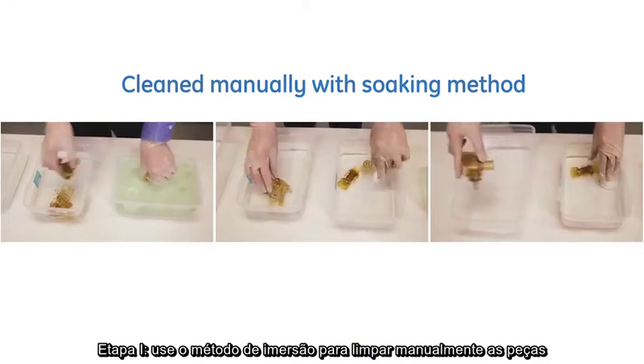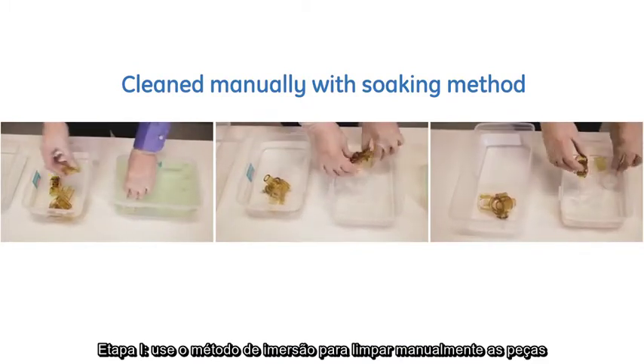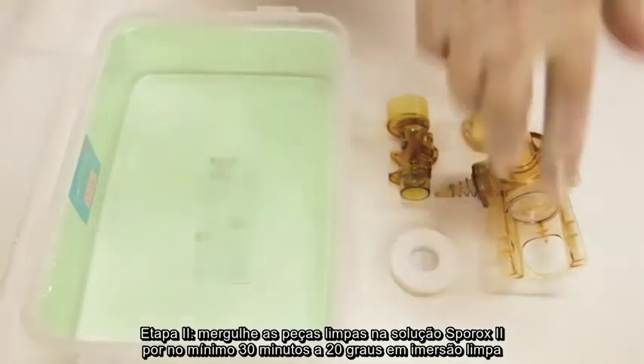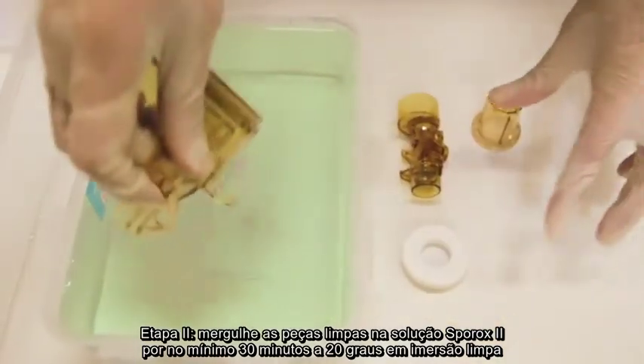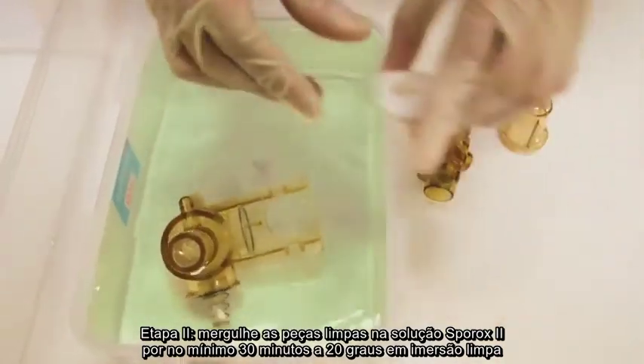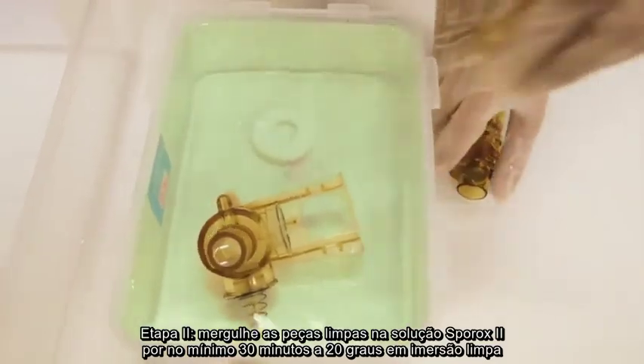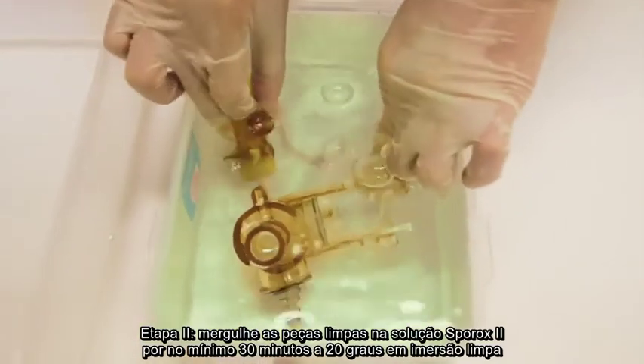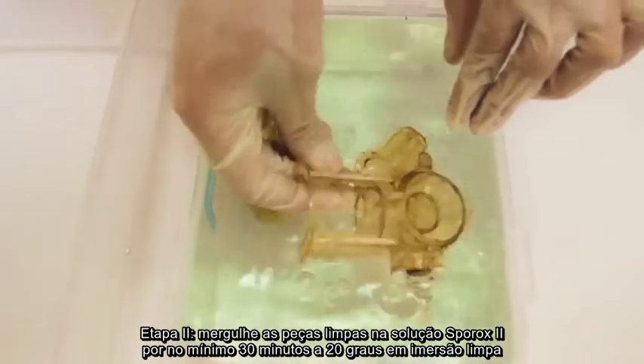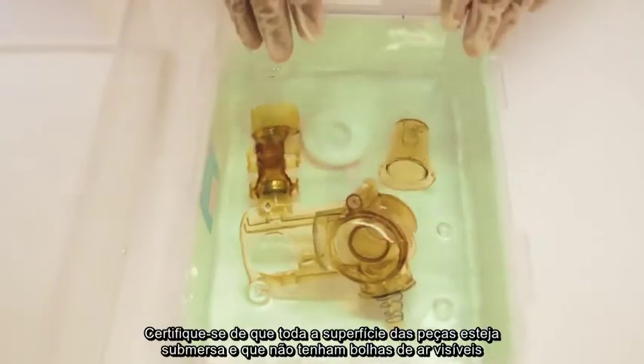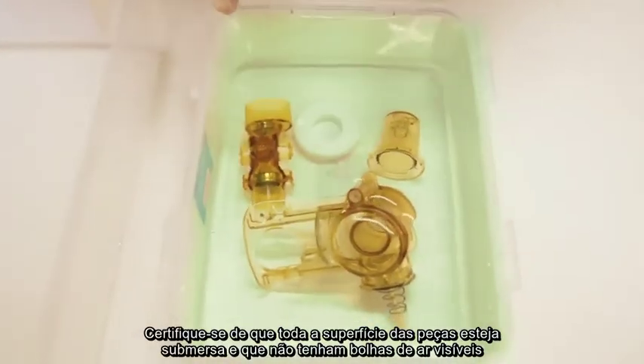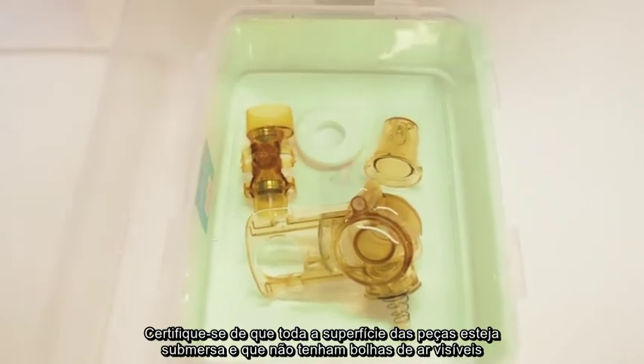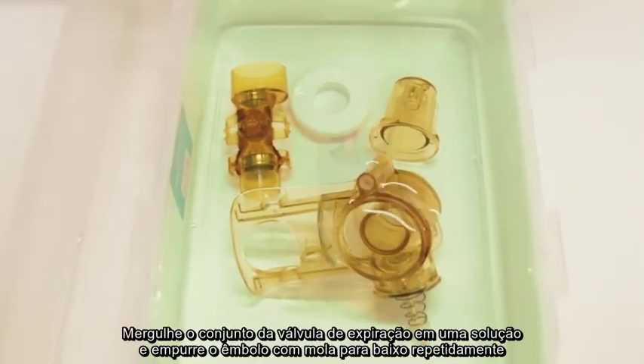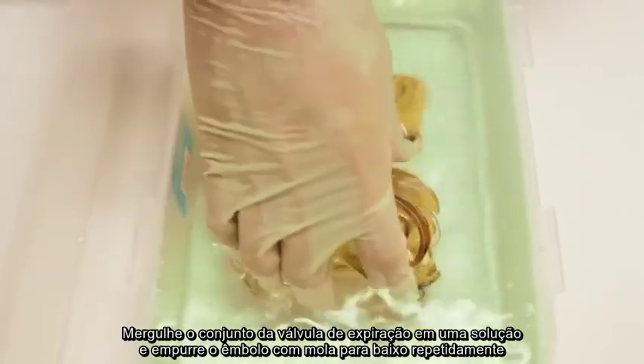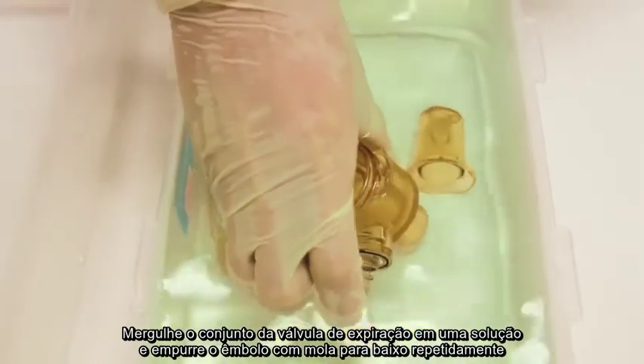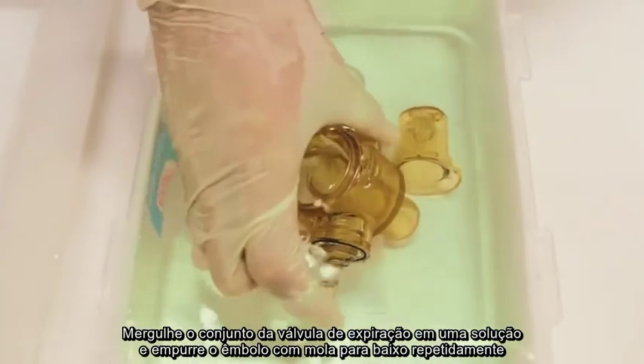Step 1. Use the soaking method to manually clean the parts. Step 2. Soak the clean parts in Sporox 2 solution for a minimum of 30 minutes at 20 degrees Celsius in a clean soaking tray. Ensure that all the surfaces of the parts are submerged and no air bubbles are visible. Submerge the exhalation valve assembly in the solution and push down on the spring-loaded plunger repeatedly.